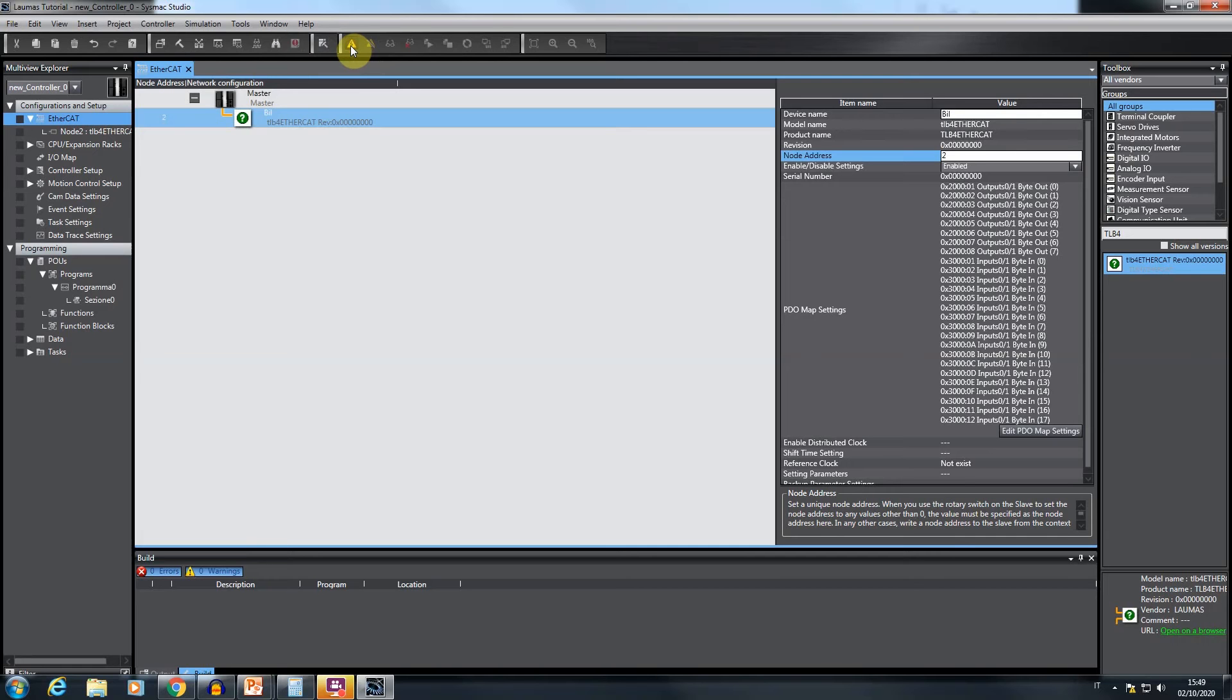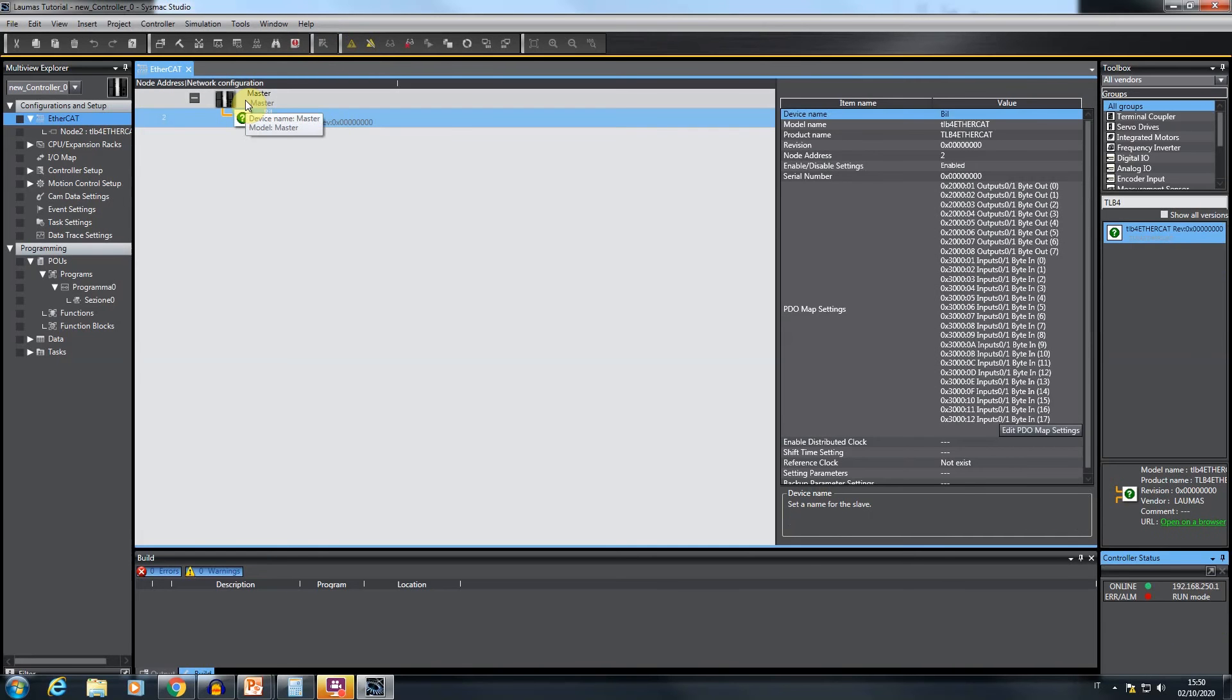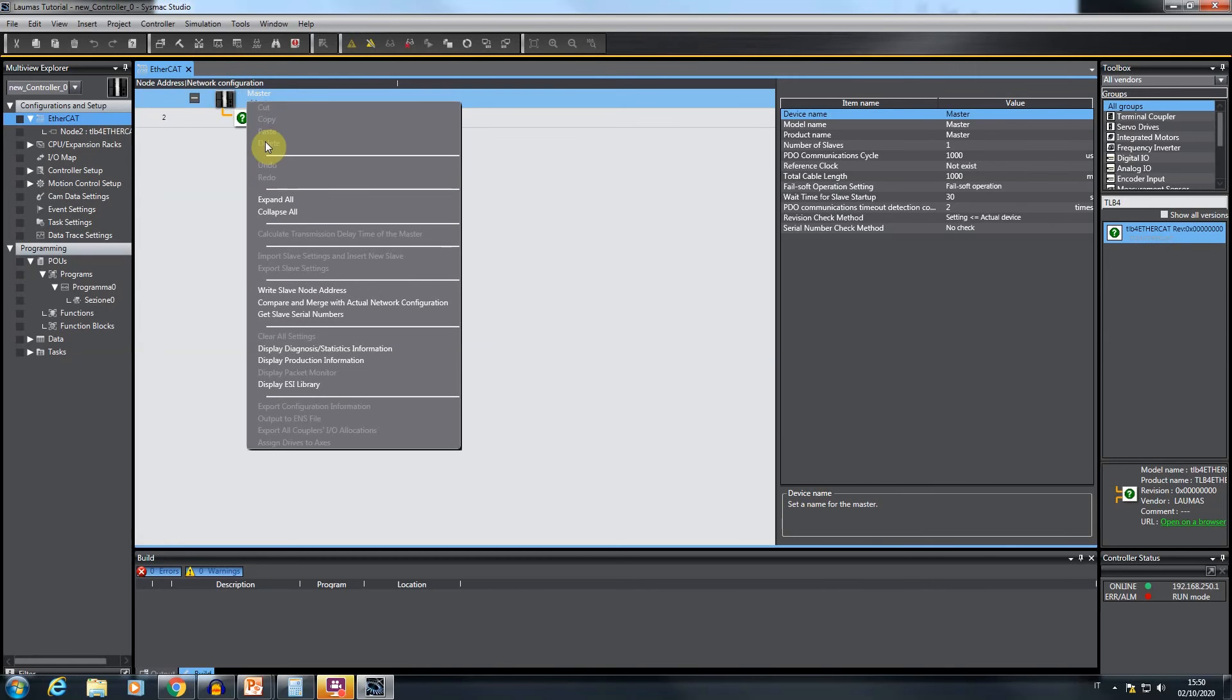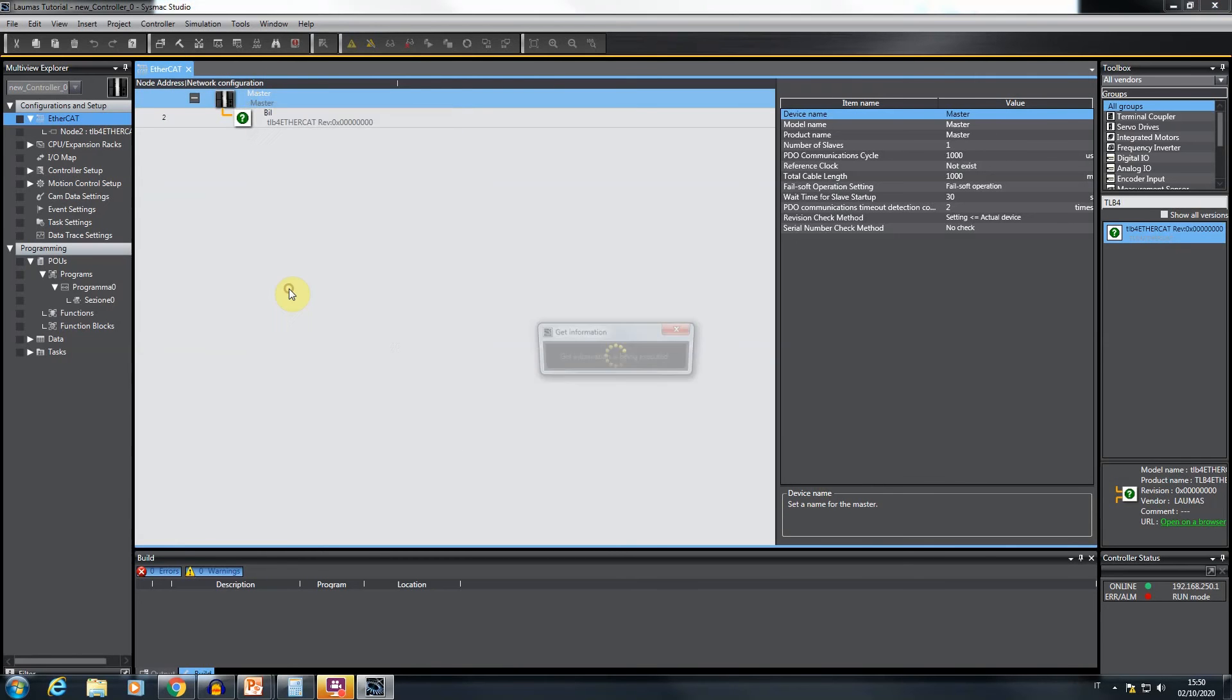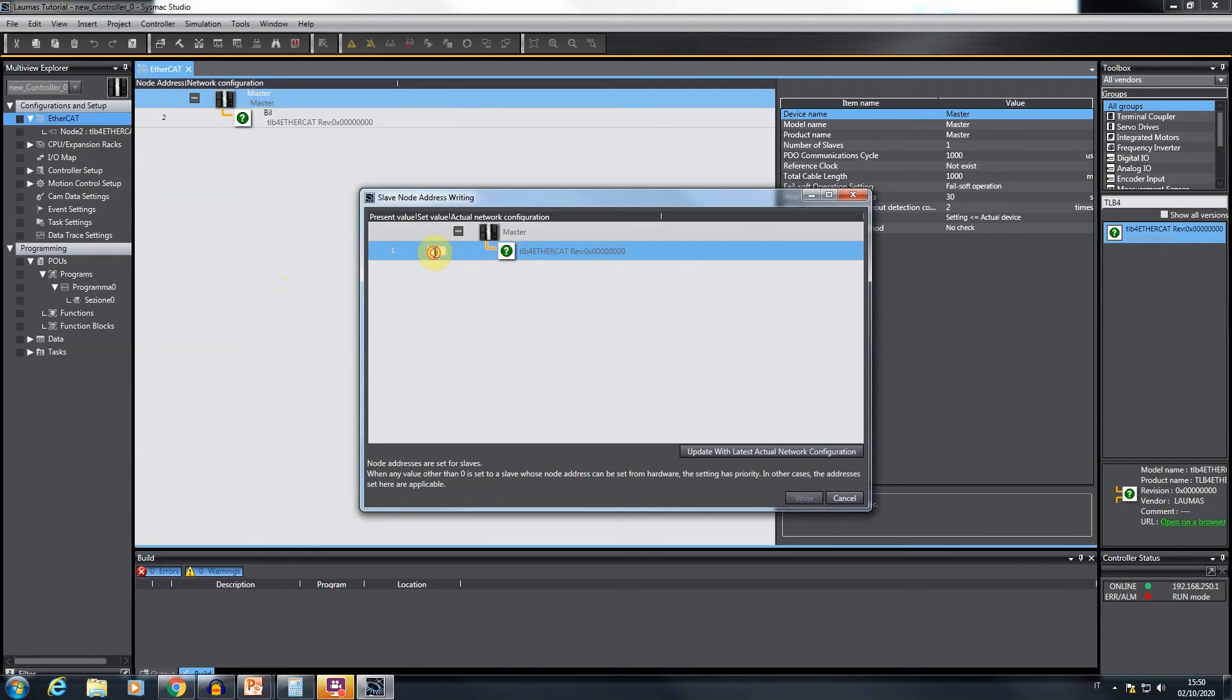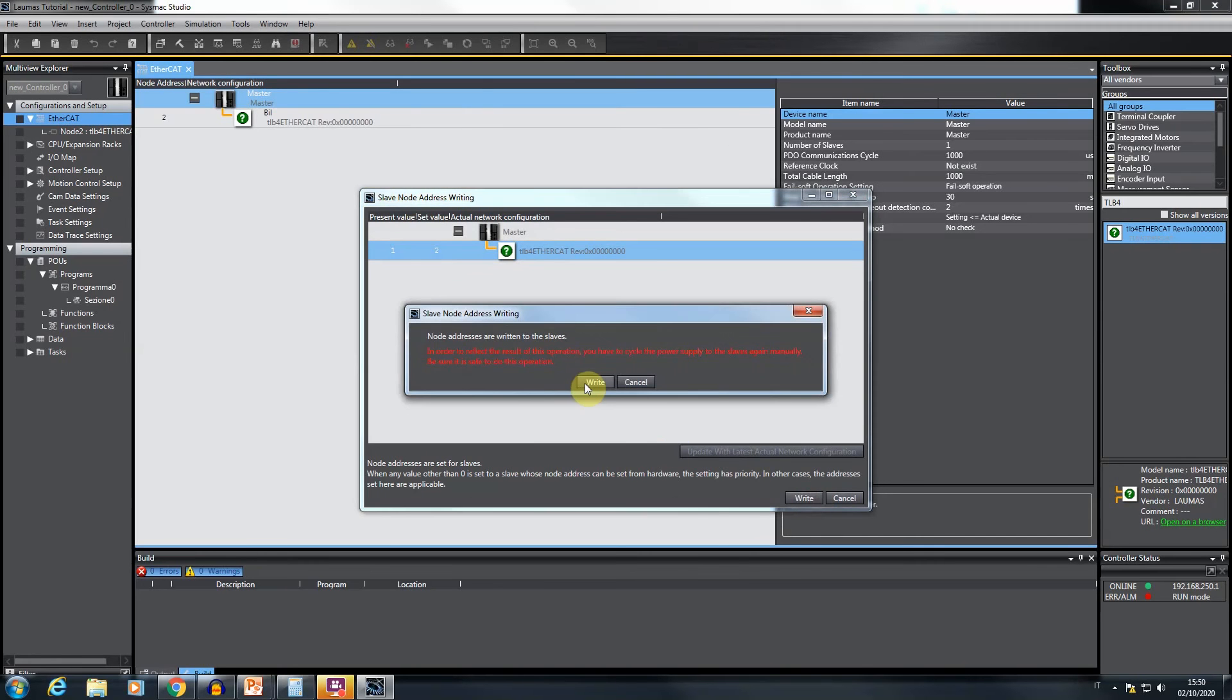To proceed, click on the specific icon to switch to the online mode. Then right-click on the PLC symbol and write slave node address. A window opens, showing all the devices recognized as connected to the PLC EtherCAT port. The TLB4 is in the list, but with the current address value equal to 1. Set this parameter to the correct value, 2, and click on write.